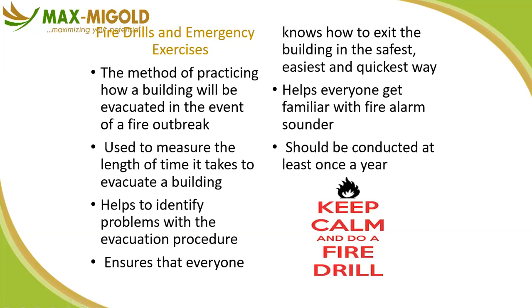Please, I've mentioned this before, fire drills and exercises need to be carried out. Not just because we need to test the system, which is actually the number one aim of a drill. Test the system working. Do we have this alarm? Is the alarm functional? If the alarm is sounded, will people respond? If people respond, where will they go to? They go to the muster point. What's going to happen there? After the muster point activity, what's then going to happen? You need to test the system.